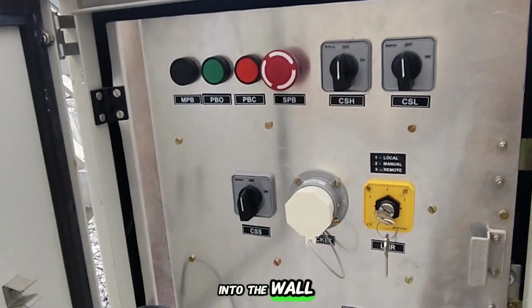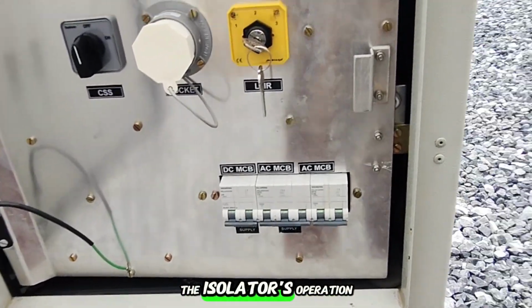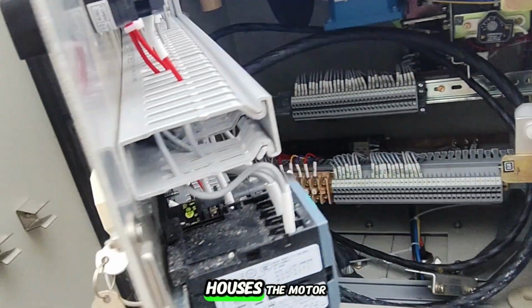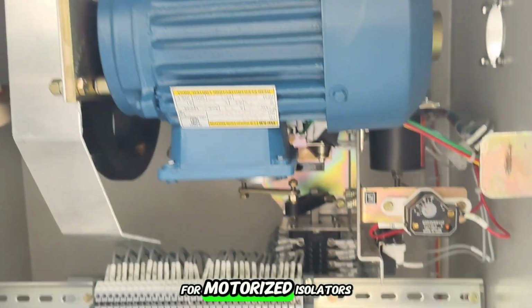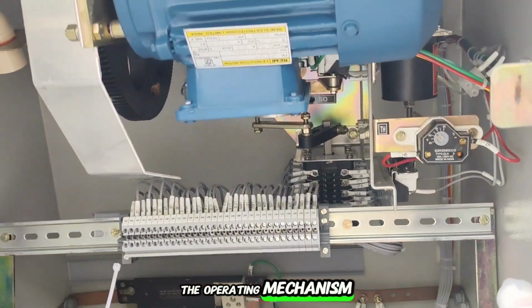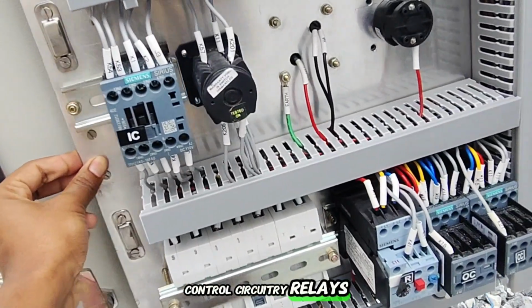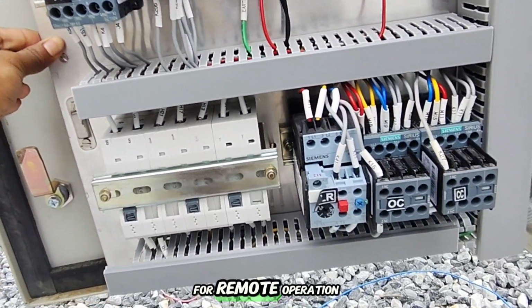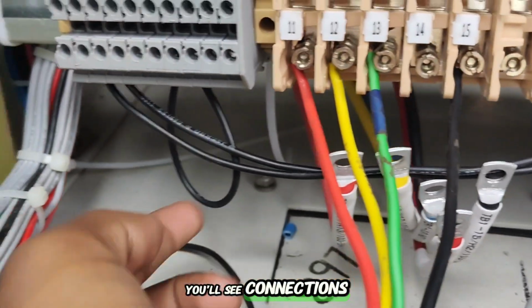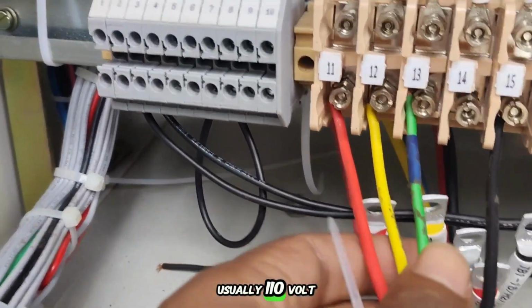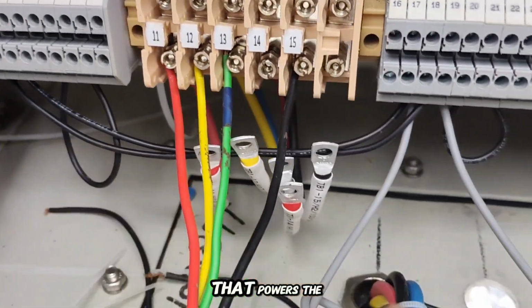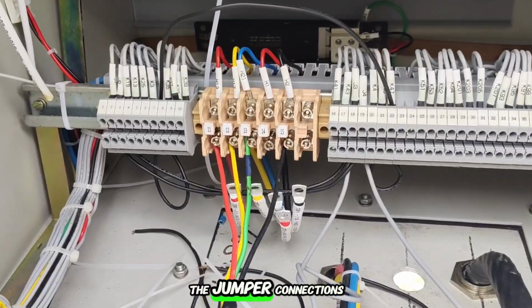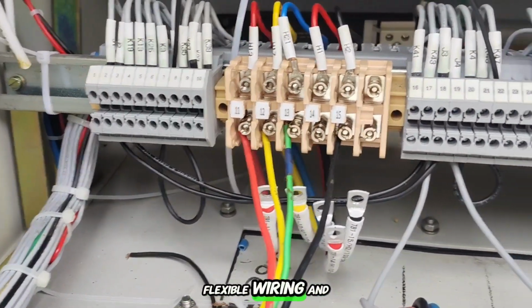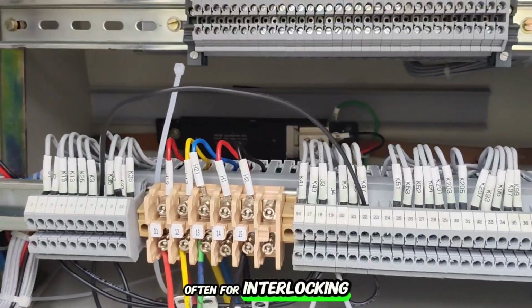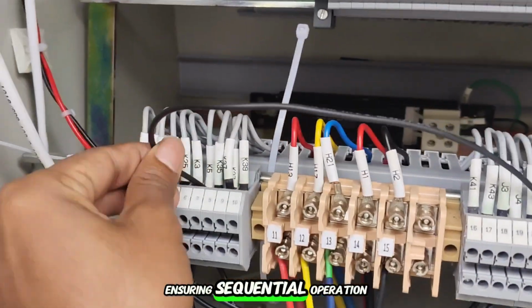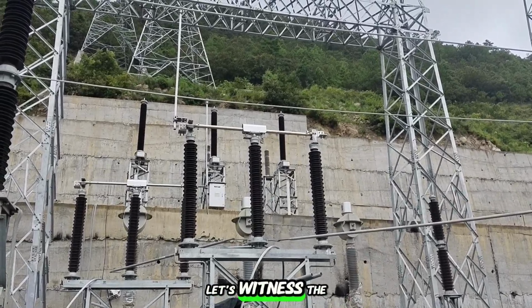Now let's dive into the control box, the brain behind the isolator's operation. This box typically houses the motor. For motorized isolators, this motor drives the operating mechanism. Control circuitry, relays, contactors, and terminal blocks for remote operation and interlocking. You'll see connections for the DC supply, usually 110 volt or 220 volt DC, that powers the motor and control circuits. The jumper connections here allow for flexible wiring and configuration, often for interlocking or status signaling, ensuring sequential operation with other equipment. Let's witness the operation.